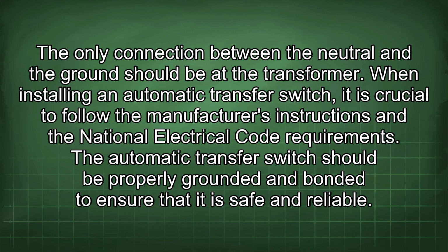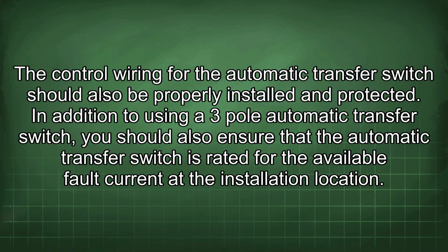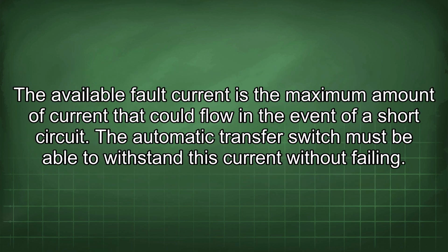When installing an automatic transfer switch, it is crucial to follow the manufacturer's instructions and the National Electrical Code requirements. The automatic transfer switch should be properly grounded and bonded to ensure that it is safe and reliable. The control wiring for the automatic transfer switch should also be properly installed and protected. In addition to using a 3-pole automatic transfer switch, you should also ensure that the automatic transfer switch is rated for the available fault current at the installation location. The available fault current is the maximum amount of current that could flow in the event of a short circuit. The automatic transfer switch must be able to withstand this current without failing.